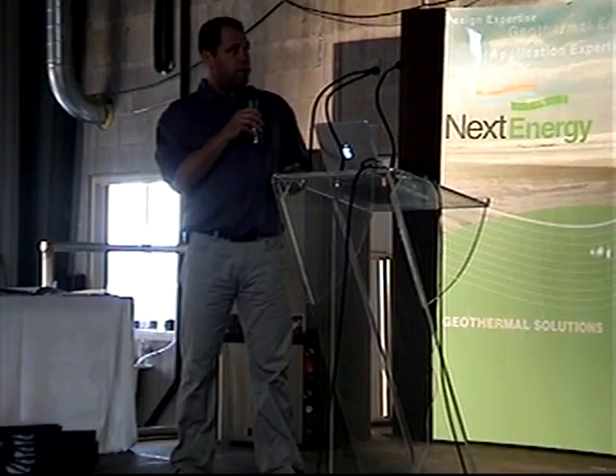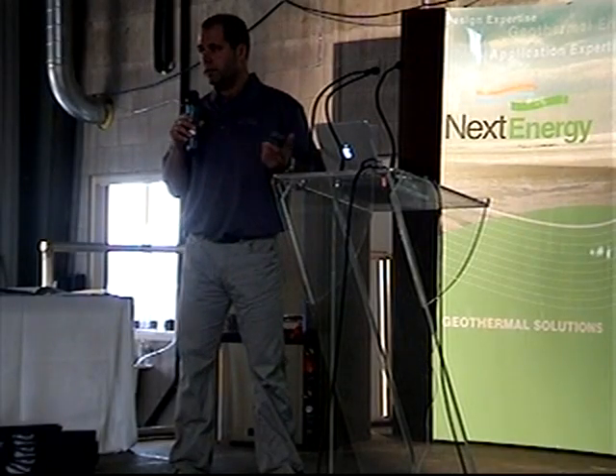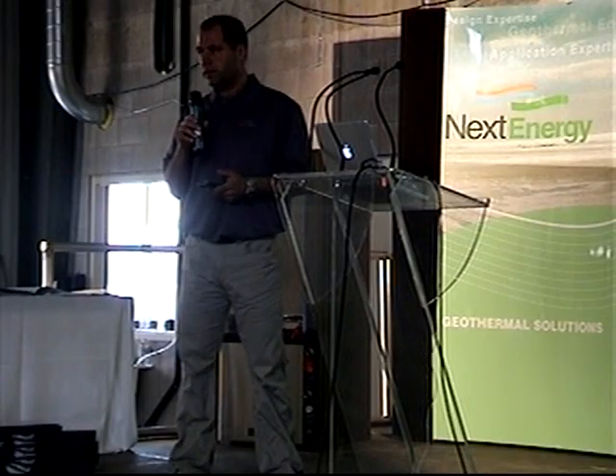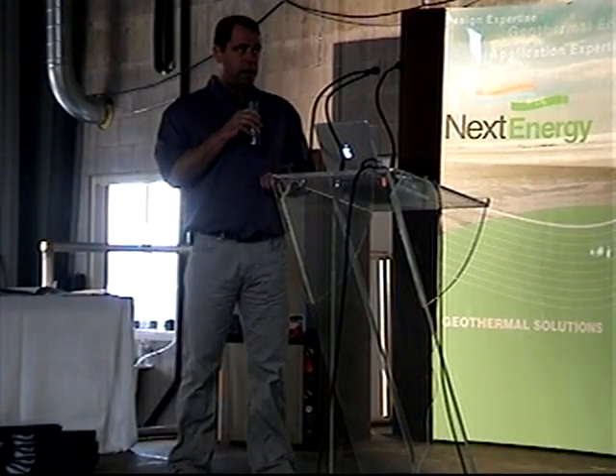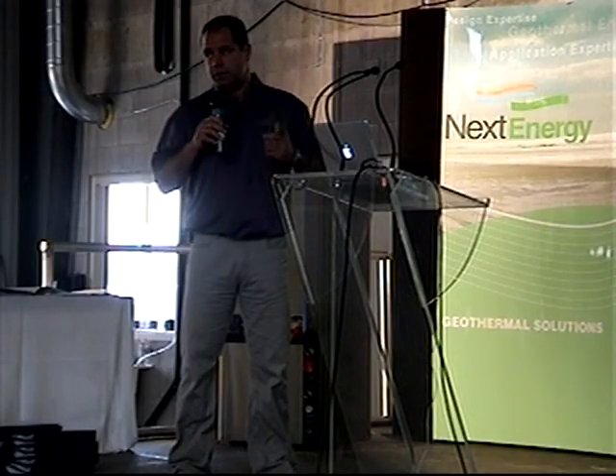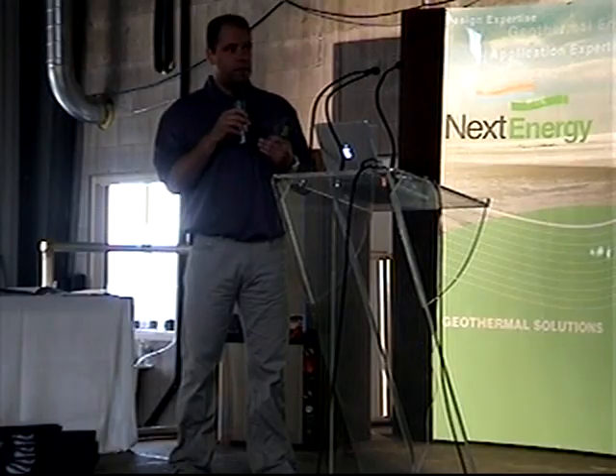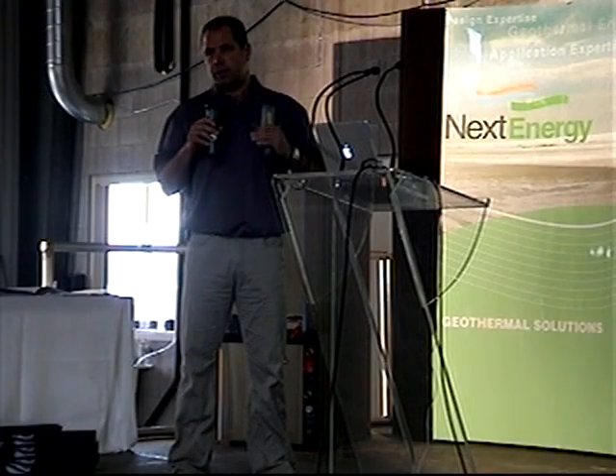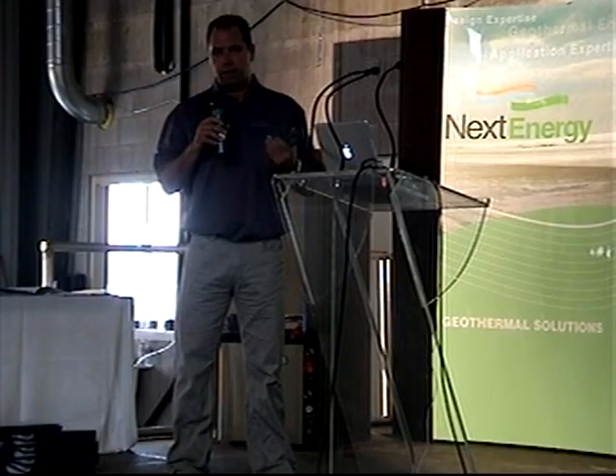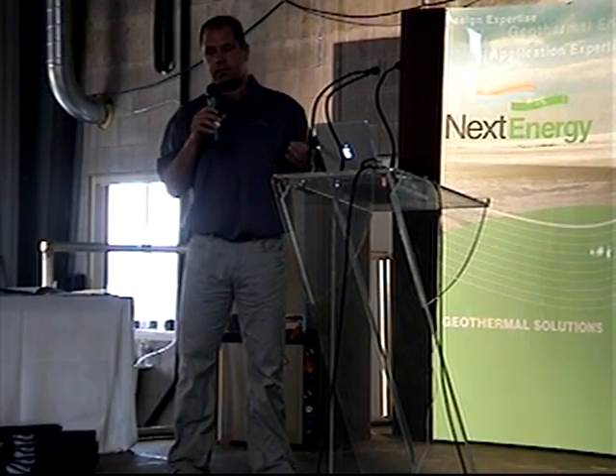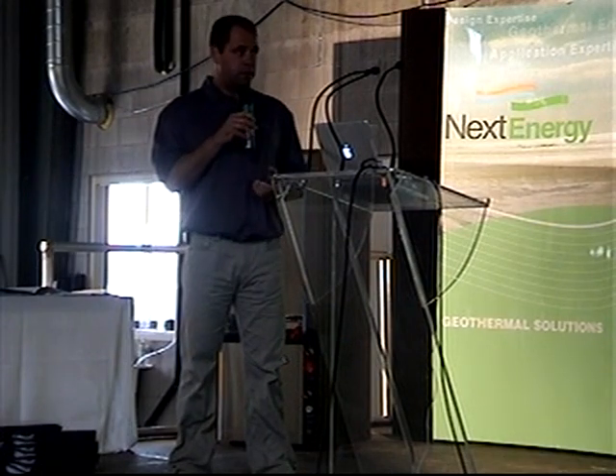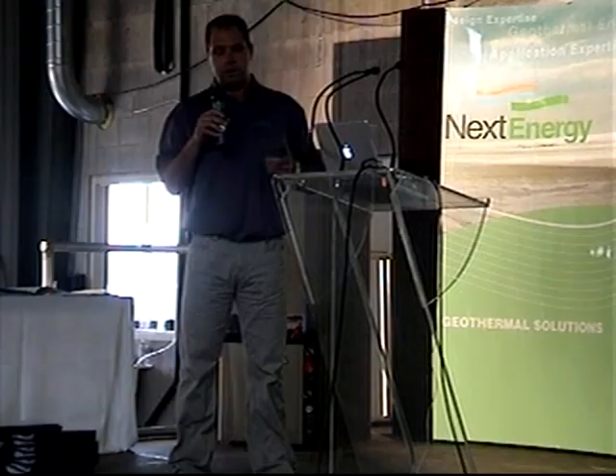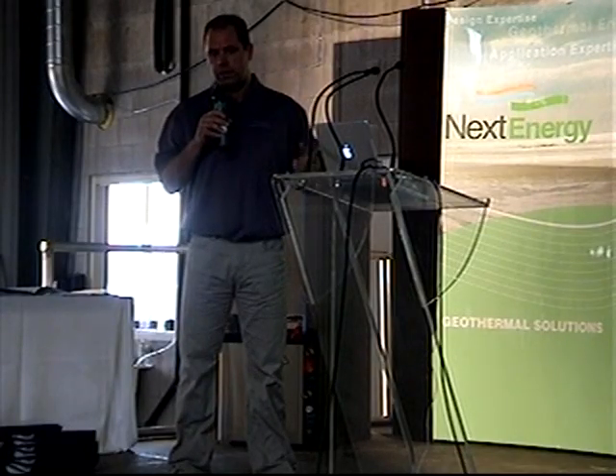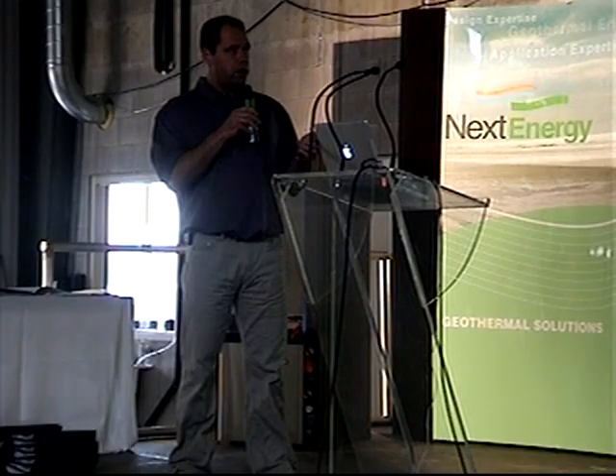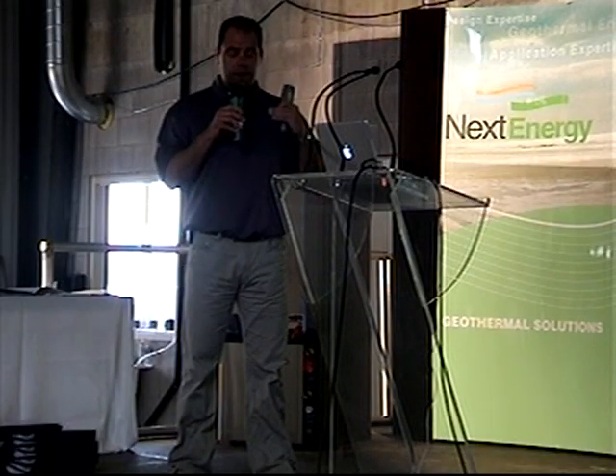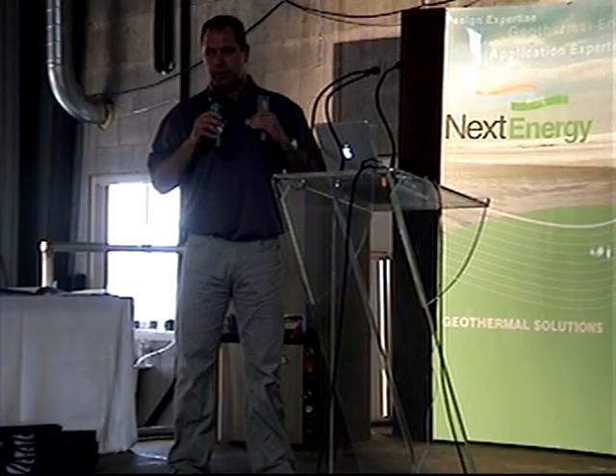All right, superheat. How many of you guys know how to measure superheat or have measured superheat? A couple of yous. Superheat is basically, refrigerant has what's called a saturation temperature, and that is, at any given pressure, there's a temperature at which refrigerant is saturated, which could mean 90% liquid, 10% vapor, or it could mean 10% vapor, 90% liquid. Doesn't matter. All it means is it's not 100% liquid or not 100% vapor. What superheat is, is how much warmer the refrigerant is than that saturated temperature.